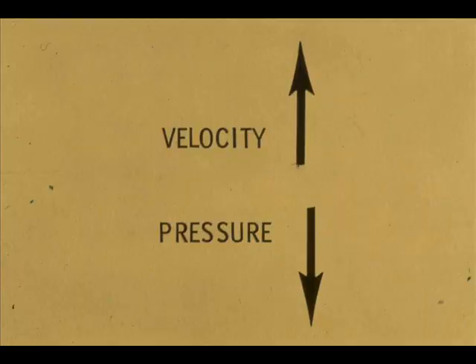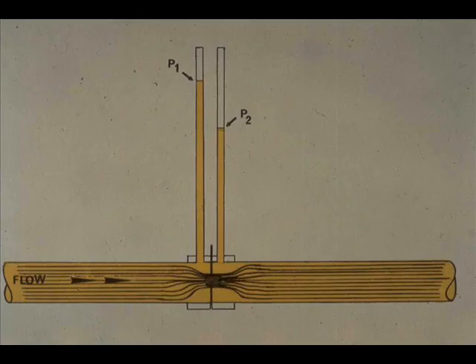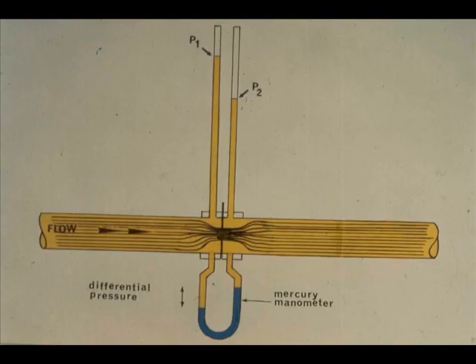As the velocity goes up, pressure goes down. This same principle applies when an orifice plate is used. P1, just ahead of the orifice, is the highest pressure, and P2, just beyond the orifice, is the lowest pressure. To measure the pressure drop across the orifice, we could install a mercury manometer — a U-shaped tube filled with mercury — connected to points P1 and P2. The higher pressure at P1 forces the mercury upward toward P2. The difference in levels is the delta P across the orifice for a particular flow rate.